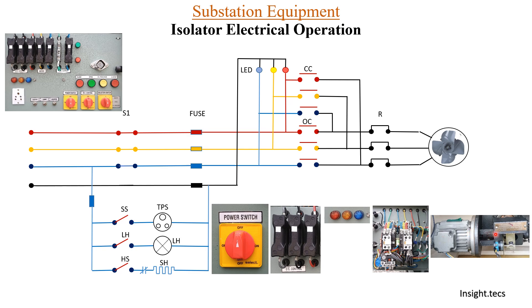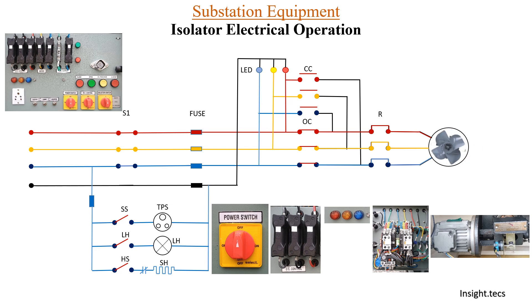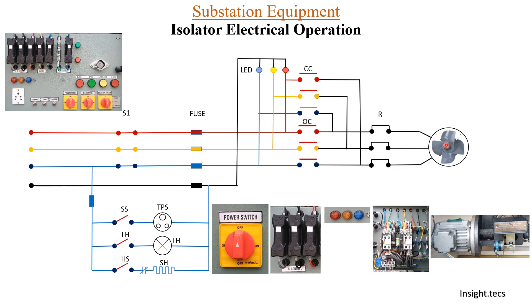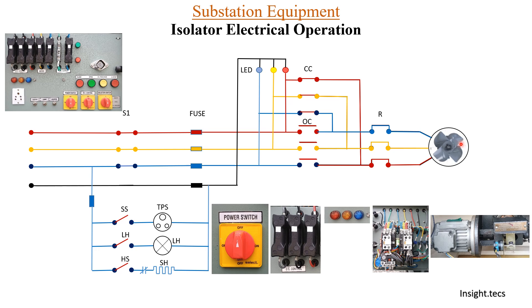When the switch is on, through the fuse and LED, the contactors will be closed. OC means open contactor — when the open contactor is closed, the motor moves in a direction such that the isolator will be opened. When CC, the closed contactor, is closed, the phases are interchanged and the motor rotates in the reverse direction such that the isolator will be closed.